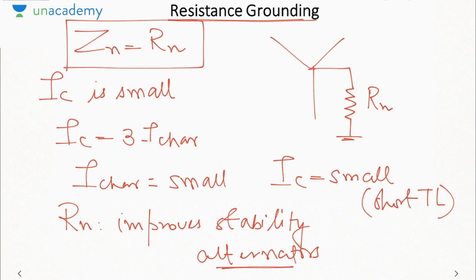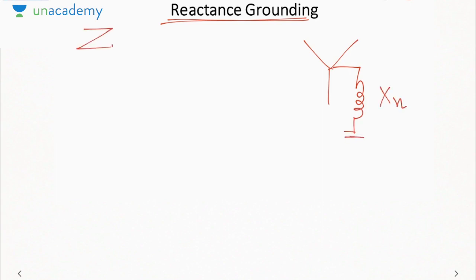There you can use resistance grounding, and it will improve the stability of the system, but it cannot cancel the line charging current. Now if you have to cancel the line charging current, you will have to use reactance grounding. That is, neutral will be grounded by means of a reactance Xn. So here Zn will be equal to j times Xn. It will be purely imaginary. That is the neutral impedance.